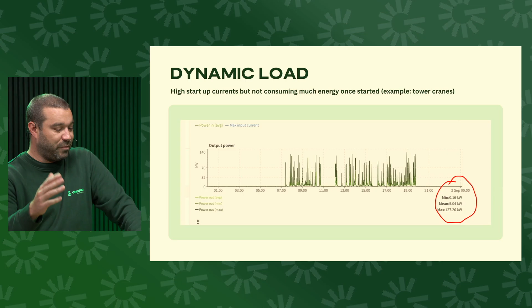So again, you can see from the load profile on the screen that when the cranes aren't being used, the load is zero, or in this case the minimum of 0.16. I suggest they actually turn them off. But again, high peaks, maximum of 127 kilowatts, jumping around all day as the cranes operate. But looking at the mean value there, despite very high peaks of 127 kilowatts, the mean value is only 5.